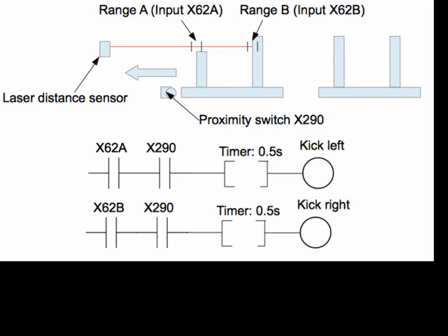Let's look at this example. I am modifying the carrier from one type to another. I want the system to keep the modified carrier left and the non-modified carrier to the right. In order to differentiate between the two, I added one laser sensor that has a different output — which is an input to the PLC — for each range that is manually configured. There is also a proximity switch to ensure that the carrier is in the right location. If I wanted to communicate that requirement to a programmer, I would send him this type of logic. This can be improved by adding timers for each device to ensure that the requirements are met for at least some time before the contact is energized. The programmer would take care of all the details, but you can communicate your requirements this way.